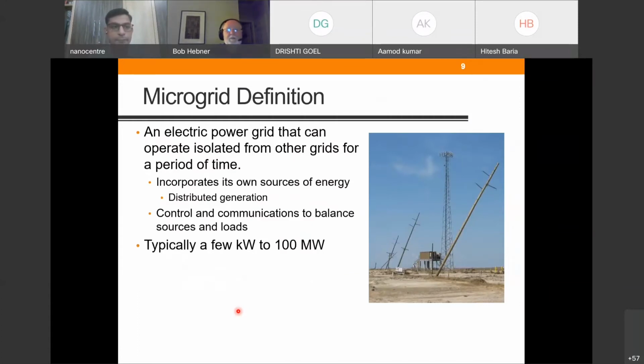Universities are expected to stay on, and similarly military bases are expected to stay on, but for very different reasons. A microgrid is a power grid that can operate isolated from other grids for a period of time, which may be minutes, hours, days, or years—that's not well defined; it depends on what it needs to do. But it has to incorporate its own sources of energy, which means it falls strictly in the definition of distributed generation. If you're going to have a microgrid, you have to have distributed generation, and you have to have the control and communications to balance sources and loads.